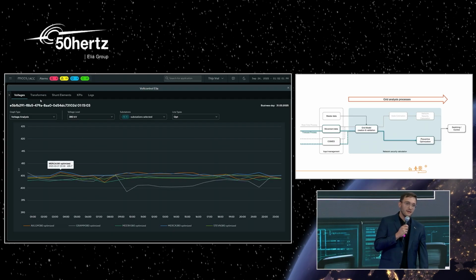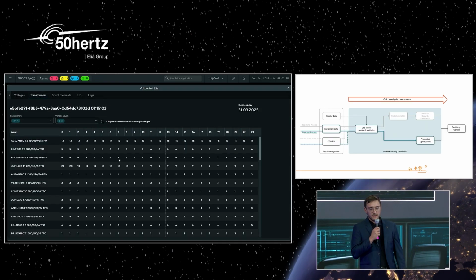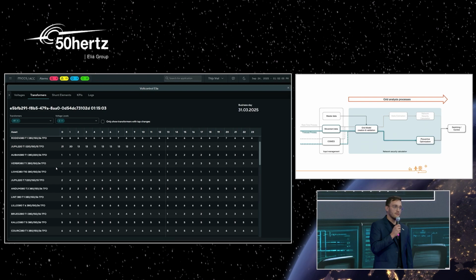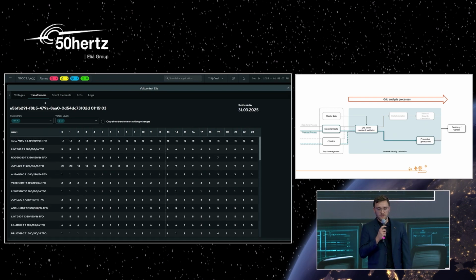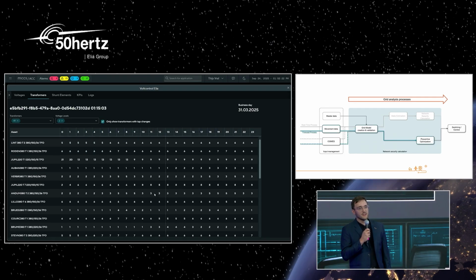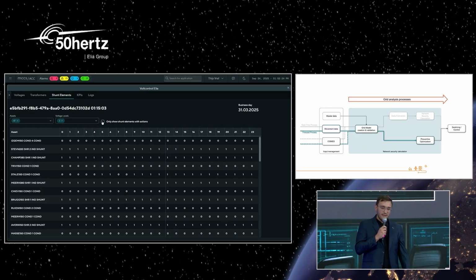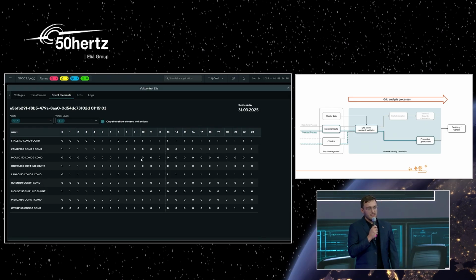Now, these voltage profiles are based on a set of actions, so let's take a look at those as well. We have certain degrees of freedom in our optimization, for instance generator reactive power set points, but also transformer taps and shunt reactor switchings. Let's filter on those that actually experience a change during the day. As you can see, we provide a complete time series of transformer taps to be implemented by our operators. The same applies for the shunt reactors — we provide the states for each hour which the operators can implement.